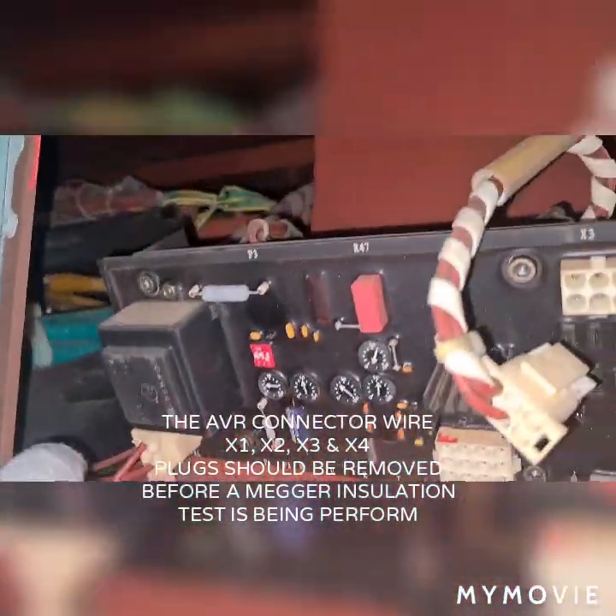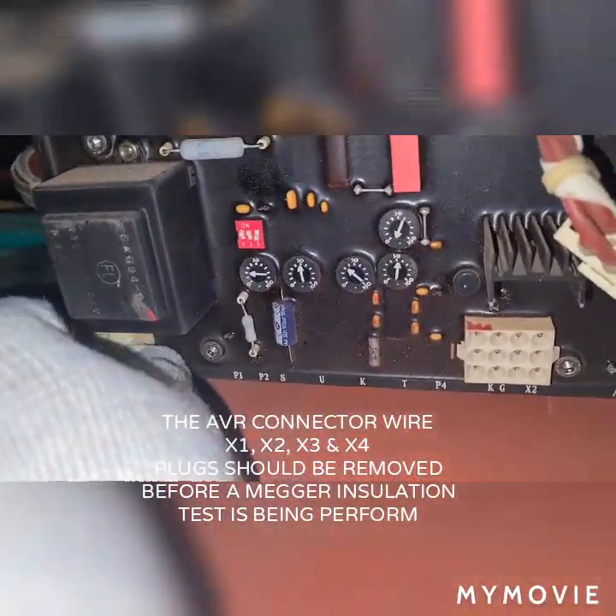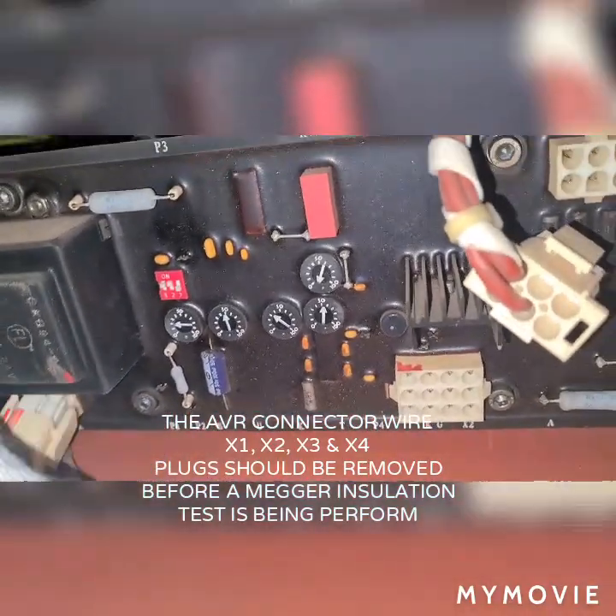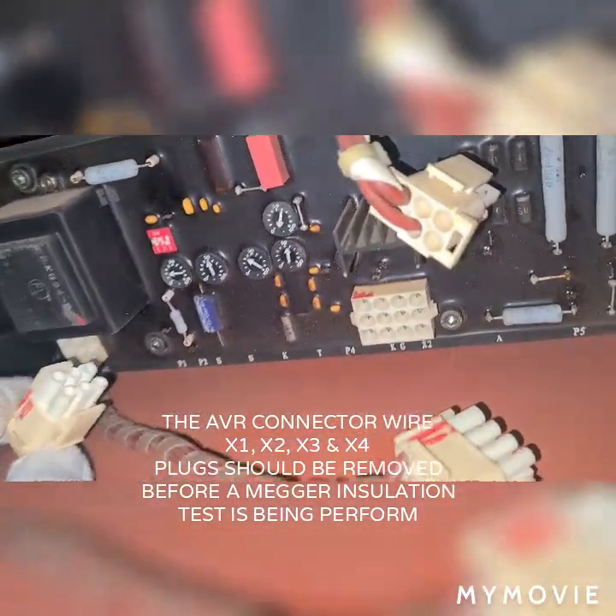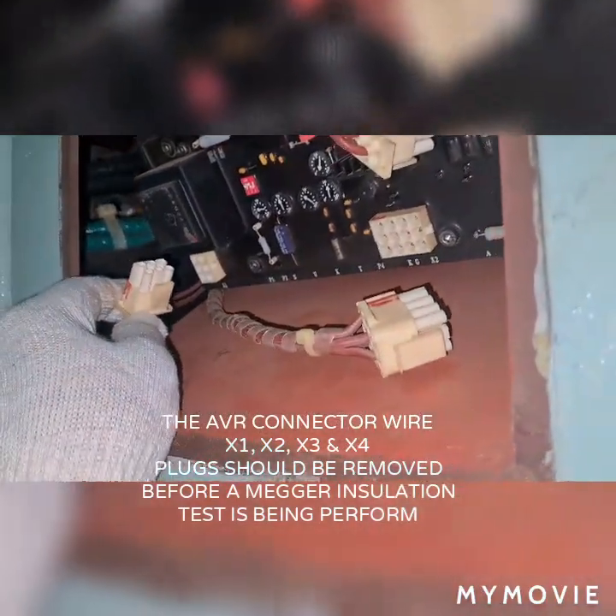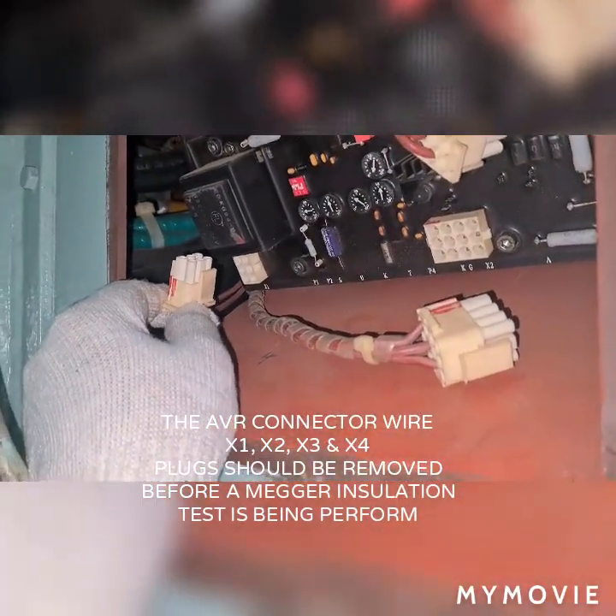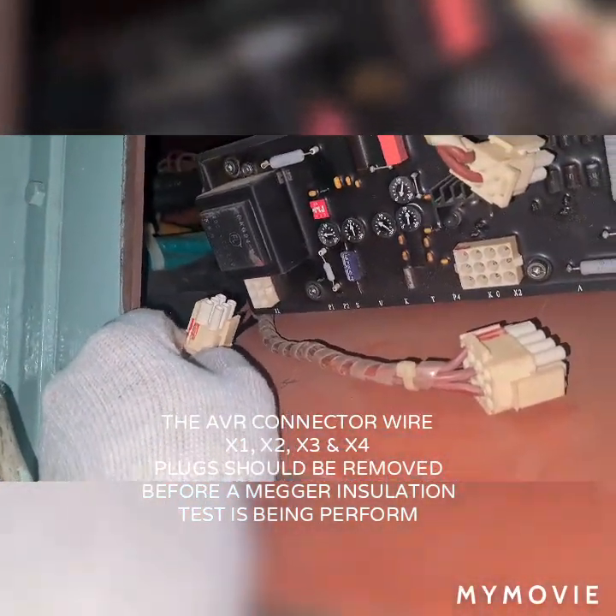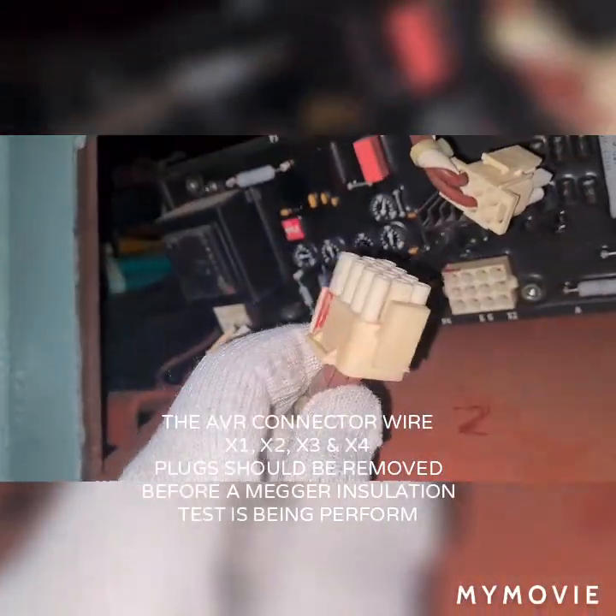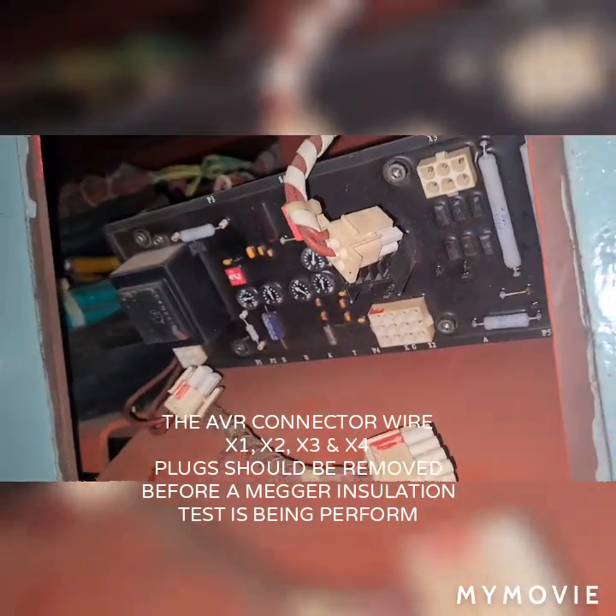R101, that is the resistor in back circuit. V22, this is a thyristor in back circuit. V101, that is a thyristor in back circuit. And V102, that is the excitation rectifiers. Make sure that all connectors X1, X2, X3, and X4 must be removed before doing a Megger insulation check.